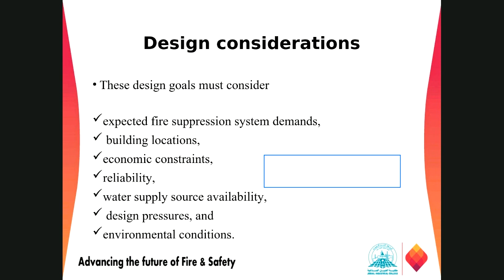So how much flow is going through the pipe? Suppose this is your pipe of 6 inch, and if you are flowing 1500 GPM through a 6 inch pipe, it is not possible. It will be possible, but we need a pump with high pressure requirement. We know the basic formula: the flow equals area times velocity. So if the area is less and we are forcing more water to go inside the piping, as per the continuity equation we discussed in hydraulics, we need high pressure to overcome the friction resistance due to the high velocity. We have to keep those things in mind. So all those parameters we have to keep in mind for designing the fire water piping.